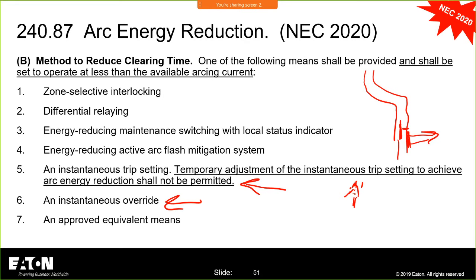And then you have the instantaneous override. The instantaneous override is not adjustable. So in a lot of cases, especially if you're not worried about selective coordination, you're probably going to meet this requirement. Especially if you're series rating things, right? If you're not worried about where the fault current is, as long as it's less than the interrupting rating, the arcing current rating could be in the instantaneous region. You're going to have to go through and make sure that's the case.